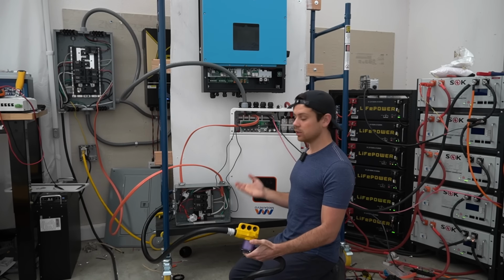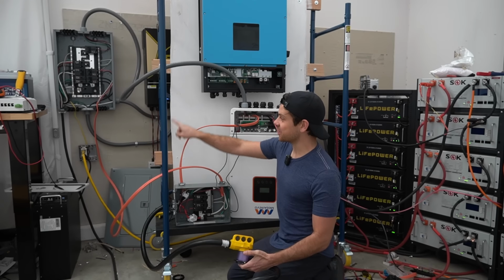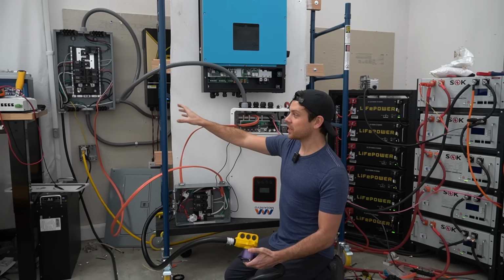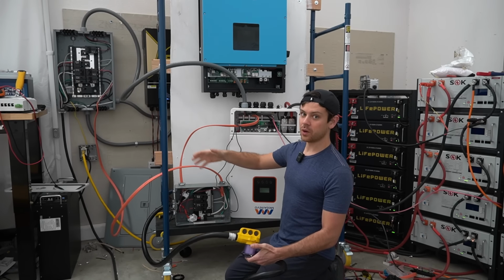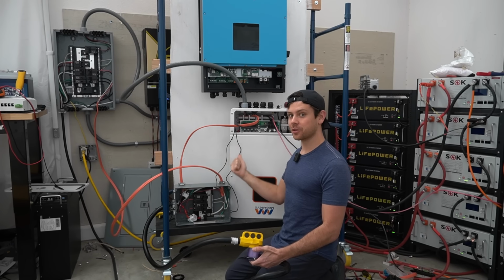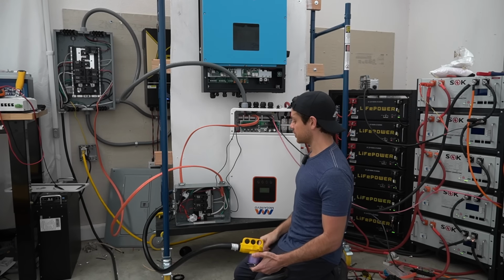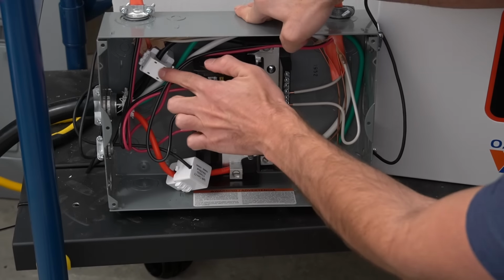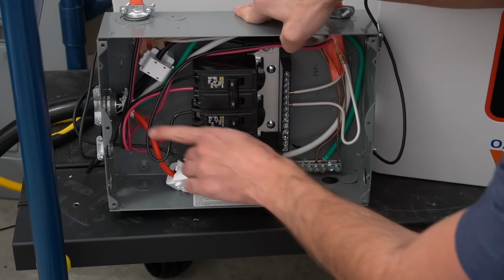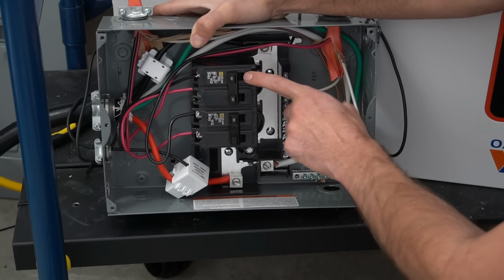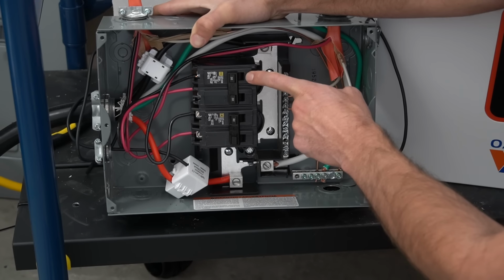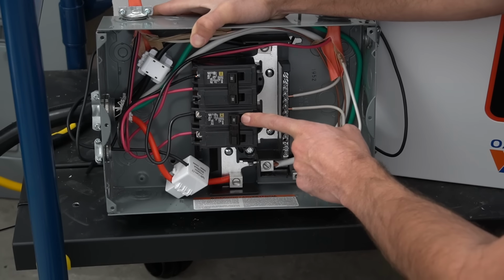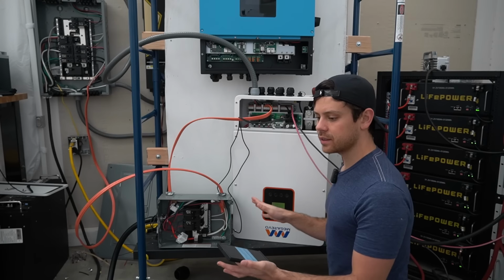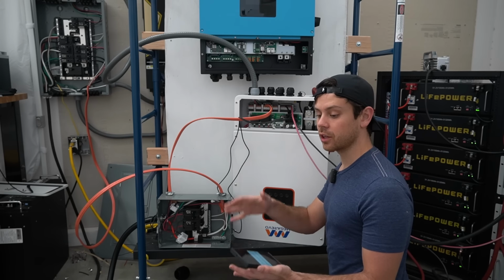And now we need a load. So this conductor goes over there to the load center so we can run the shop's heat pump without backfeeding the grid and through the AC input. So this should be really fun. And these CTs are directional, so you have to ensure that the arrow is facing towards the supply. We have a 30 amp breaker going to the AC input of the 8K and a 50 amp breaker going out to the load.